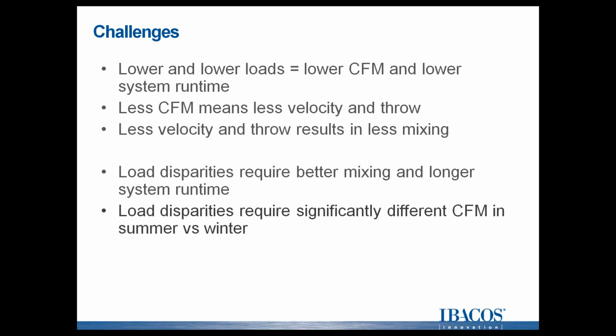So some of the challenges that we're currently seeing: lower and lower loads have resulted in lower CFMs and potentially lower system runtime if the system is oversized. That reduced CFM means less velocity and throw, and in turn that results in less mixing both within a room and within the whole house. So we have a challenge here to continue to provide adequate comfort while working with a lot less air. And on top of that, these load disparities between the winter and the summer also require better mixing and longer system run times in order to adequately condition those exterior rooms that could potentially be sun tempered. And we'll see this issue coming up in some of the data that we'll look at. So that different CFM between summer and winter presents a challenge.